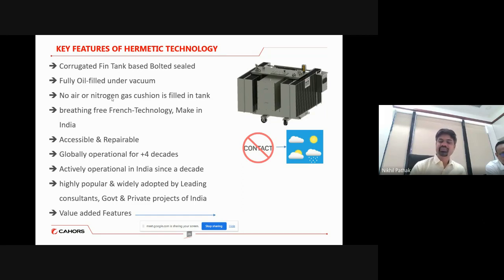So we are suggesting that for a hermetically sealed transformer, the sampling of the oil should be done at an interval of 5 years. It is also included in our operational and maintenance manual of the hermetically sealed transformers. So instead of the yearly headache of maintenance, we are confirming that the transformer can be operated for 5 years, and every 5 years the oil can be sampled and checked so that the BDV healthiness can be validated from time to time.